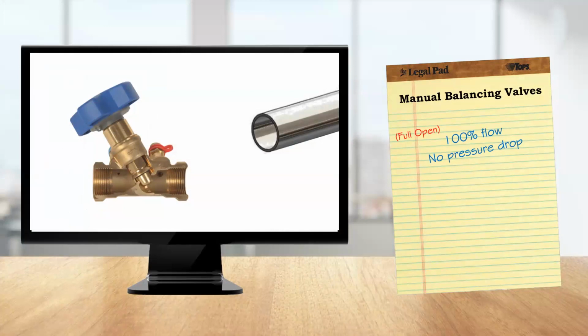To increase the pressure drop to balance the loop, the handle turns, causing the effective diameter of the opening to shrink. The opening of the pipe shrinks, representing a smaller area in which to pass the same amount of water. That's what creates your pressure loss. Moving the same amount of water through a smaller area requires energy in the form of pressure. So at 100% flow, which is a balancing condition, this smaller opening creates that 12 pounds of pressure drop that we're looking for, or pressure loss.